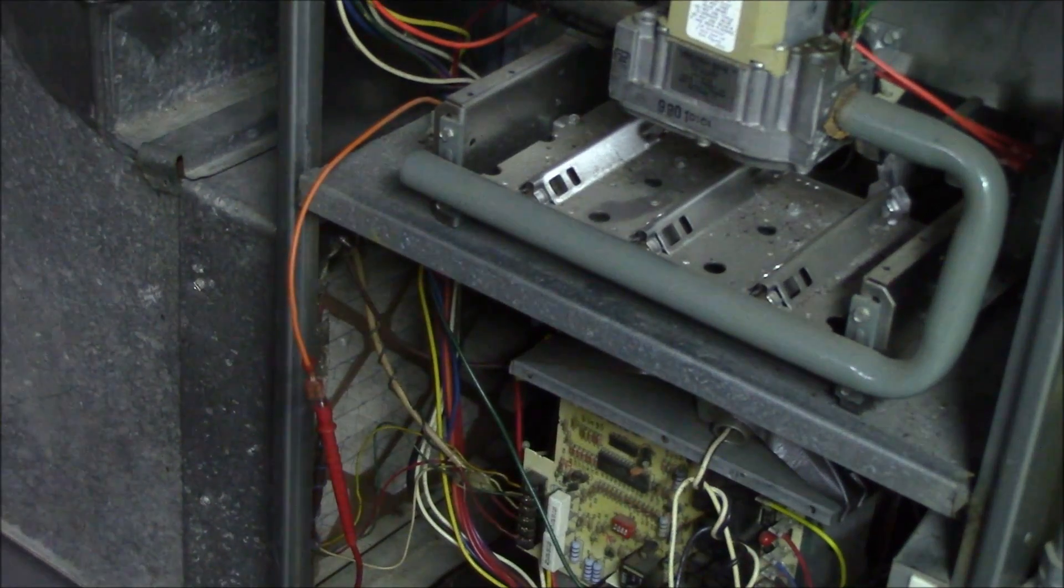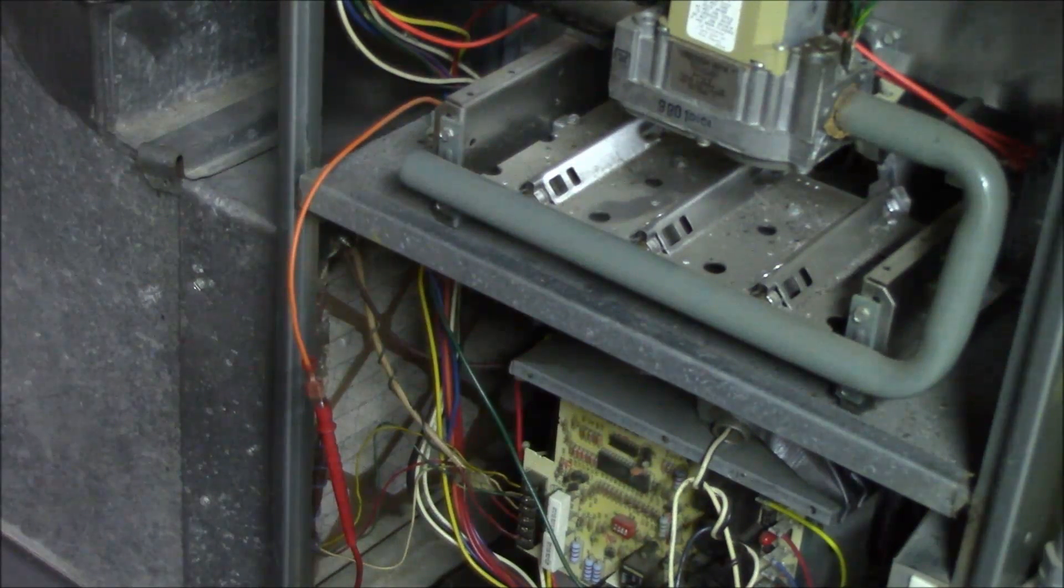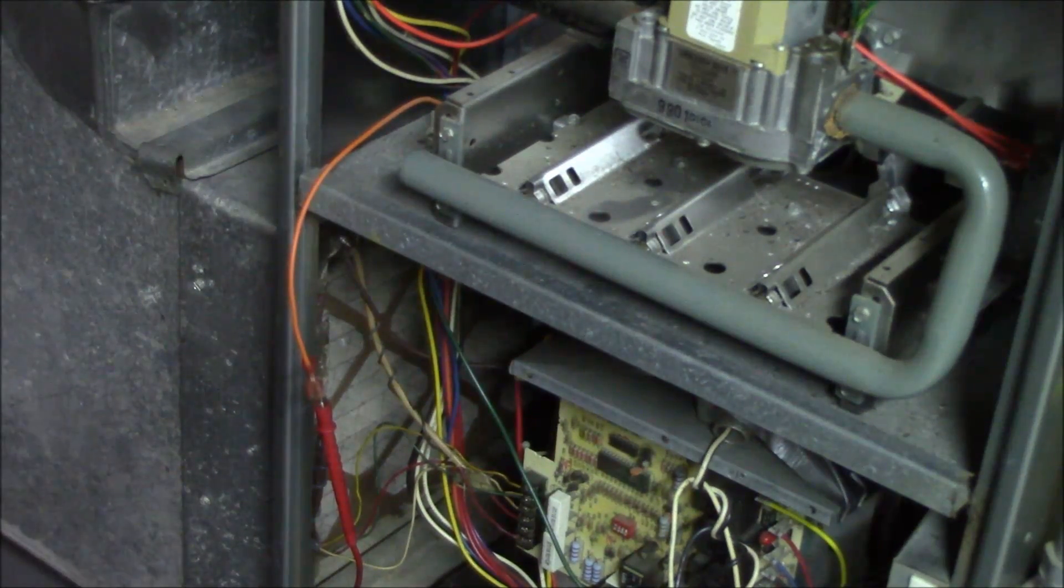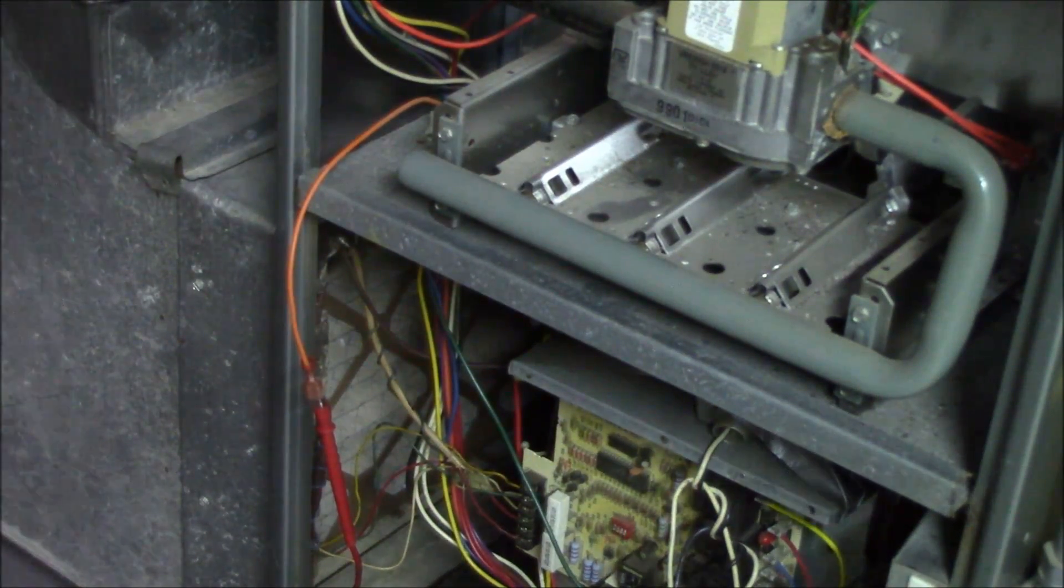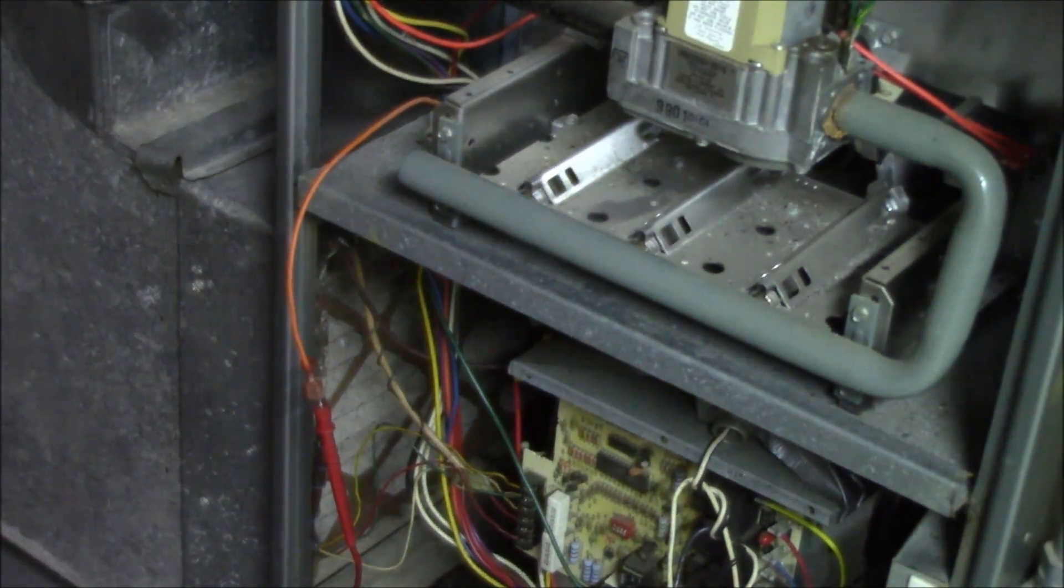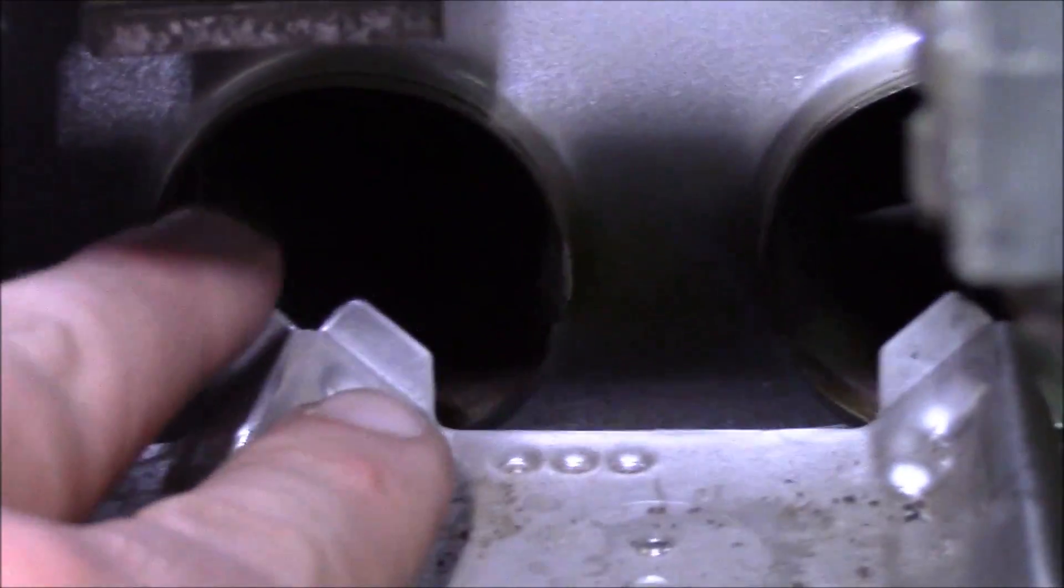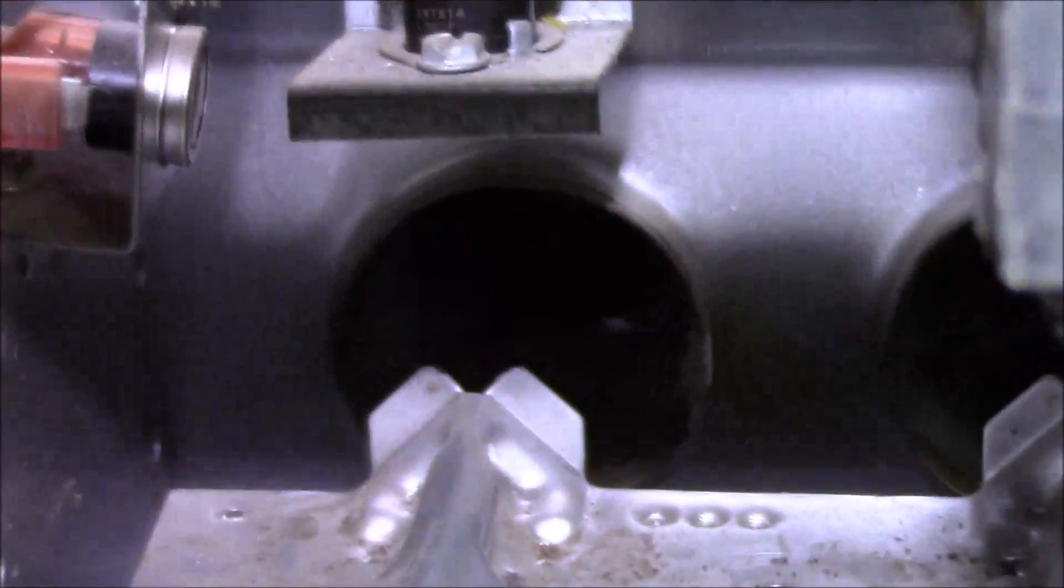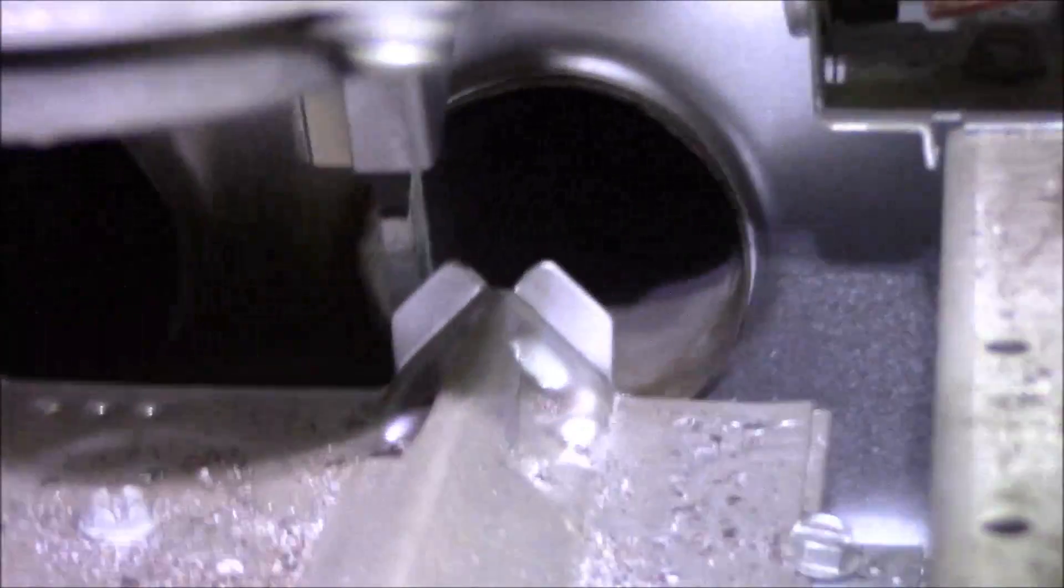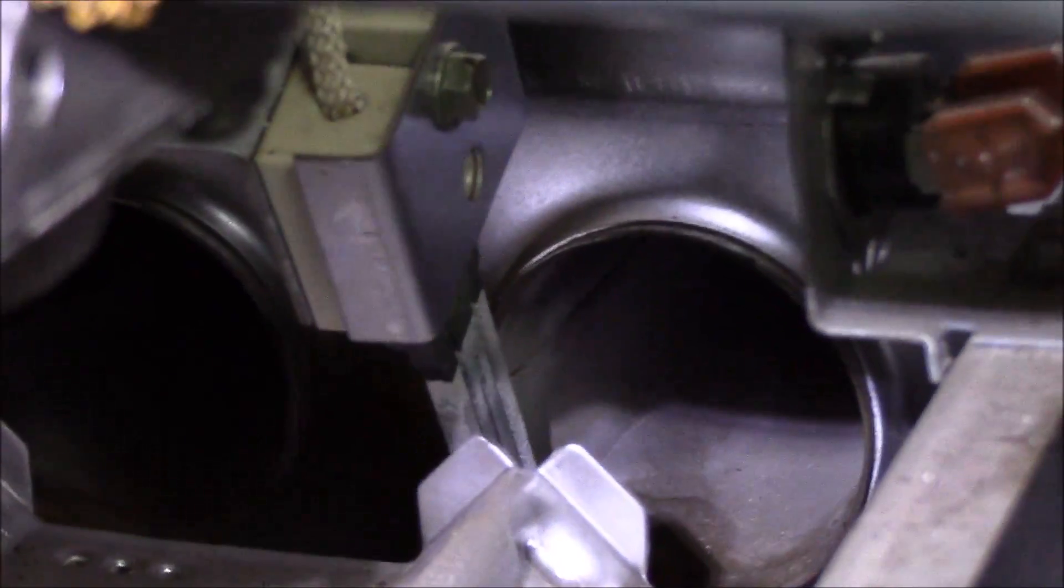One thing nobody ever thinks of: that flame sensor will sit right in front of the last burner. It's kind of a safety when you think about it. You get the hot surface igniter right there, it'll light this flame here, the crossover carries it to this burner, the crossover carries it to this burner.